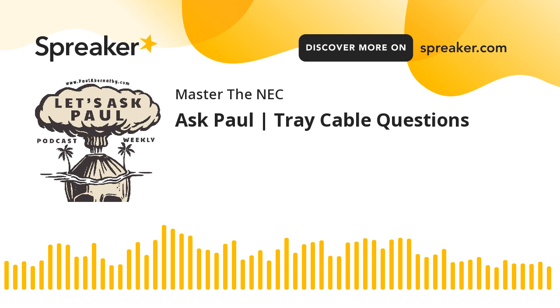Now, the inner conductors, because people ask this question all the time, inside of tray cable are the exact same type of conductors, like THHN, THWN-2, XHHW. It's the same conductors that you would pull in a raceway, no different. A lot of people get confused with that. Is it something special? It's typically not. It's the same type of insulated conductors that you would pull individually in a raceway.